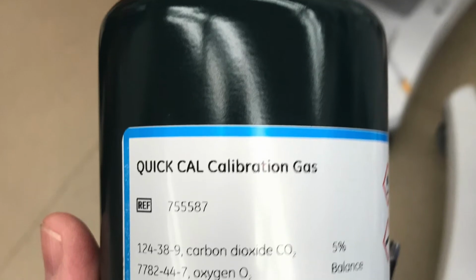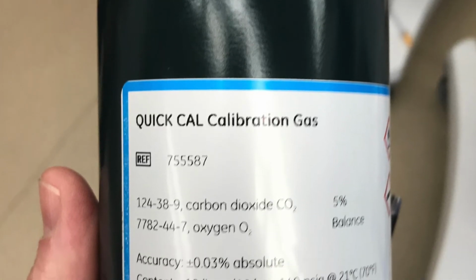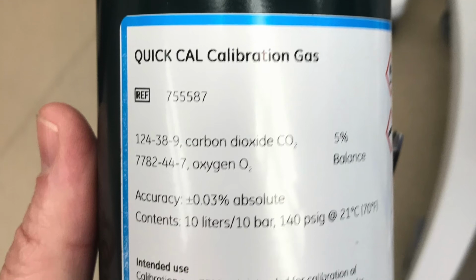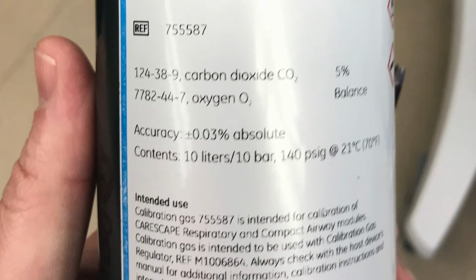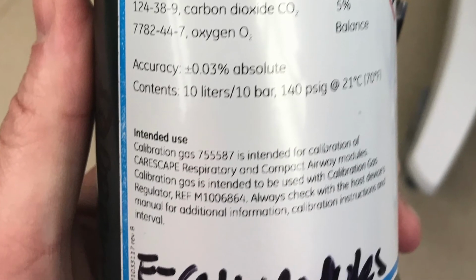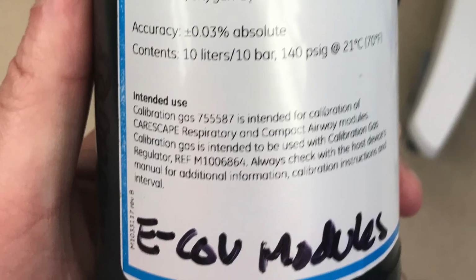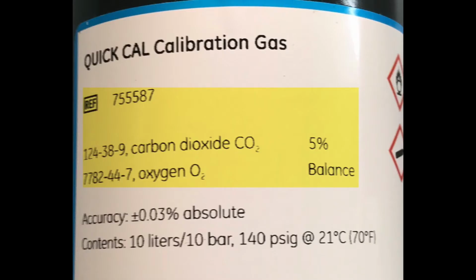What you'll need is calibration gas. Use only GE Healthcare authorized calibration gas. Do not use other calibration gases or the calibration will not be successful. Check the label and the reference number. For the US, the number should be 755587. That's the correct calibration gas.